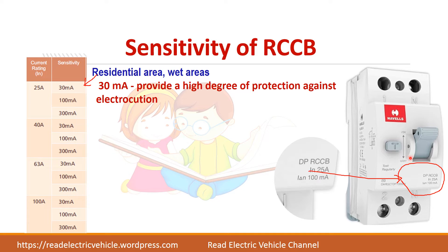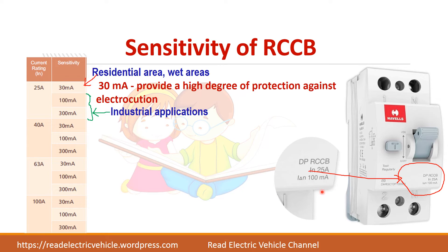For industrial applications, the sensitivity is 100 milliamps. This type of RCCB can be used where the leakage current can be high. If you go for a lower sensitivity rating, it may lead to nuisance tripping, meaning the RCCB will be continuously tripping and will affect the production process. In such cases, it is necessary to go for a higher rating. And 300 milliamps is normally preferred in places where the possibility of electrical shock is less but it is necessary to protect the area from fire.